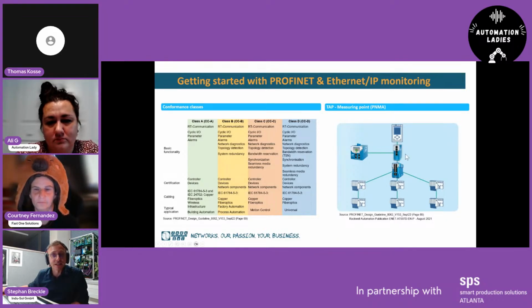For all the planning guys who may watch this web session, this is how all OT networks have to look, in my opinion, no matter if it's EtherCAT, PROFINET, Modbus TCP, or Ethernet IP. You have your PLC, after your PLC a test access point for all the analyzing, and after that a managed switch, like all IT guys use. After this managed switch, you can do what you want - star, ring, line topology with all your IO devices and other infrastructure components.